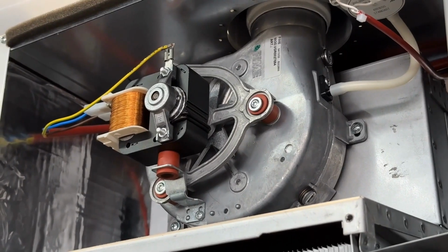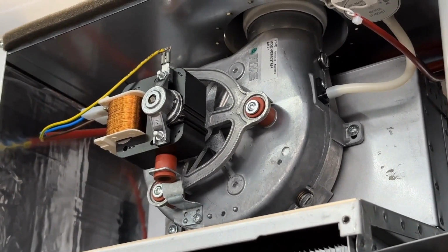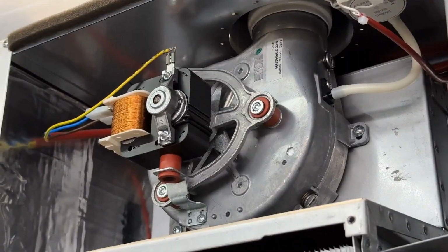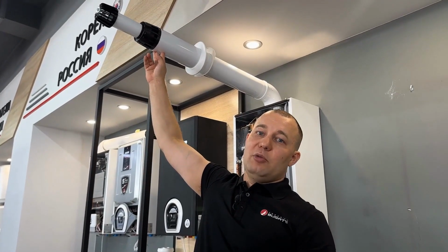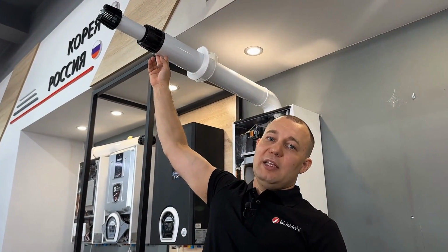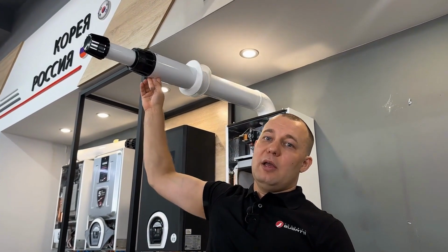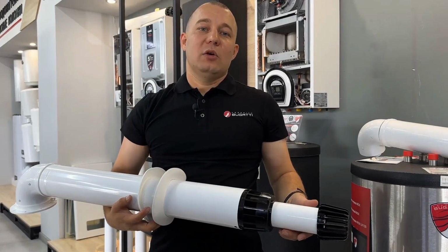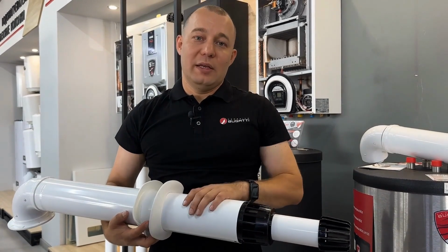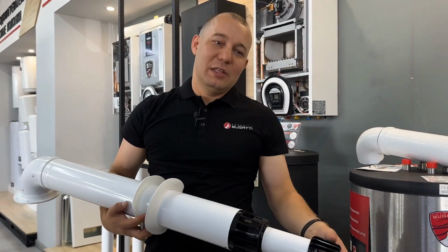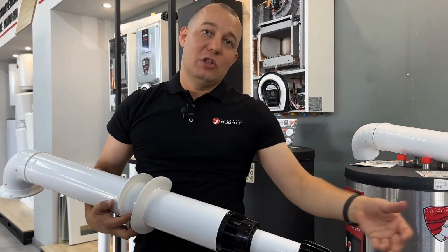After the primary heat exchanger, the now moist, cooled flue gases are sent to the chimney. It is important that the slope is between 3 to 5 degrees and that it is directed not towards the boiler but outside. Since condensate will also form in the flue, it is important that the condensate drains outside and not onto the primary heat exchanger.